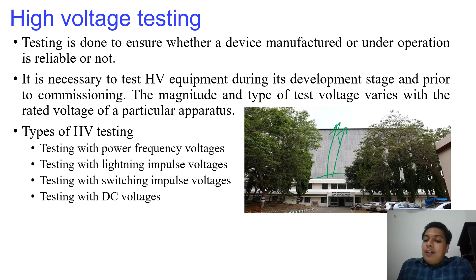Then testing with lightning impulse voltages, like the lightning overvoltage we already discussed. Under such a lightning impulse voltage, the impulse means a waveform like this: when you see the lightning, whatever voltage is impressed will have a peak for a very small fraction of time, say 1.2 microseconds, and then come down slowly to zero. That is the lightning impulse voltage.